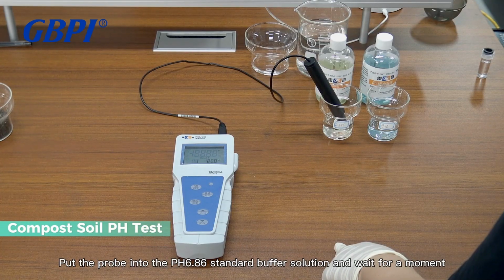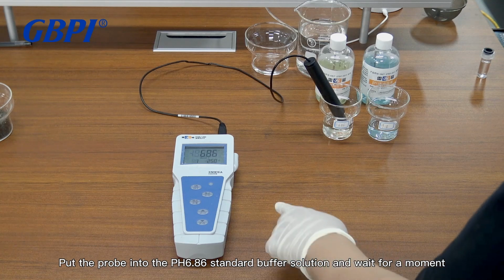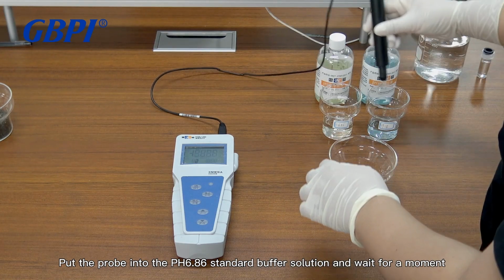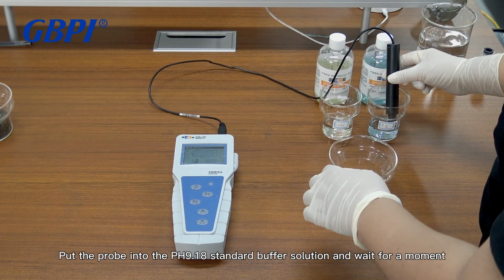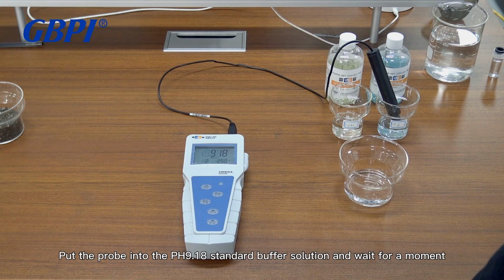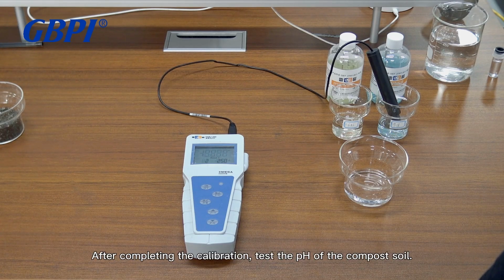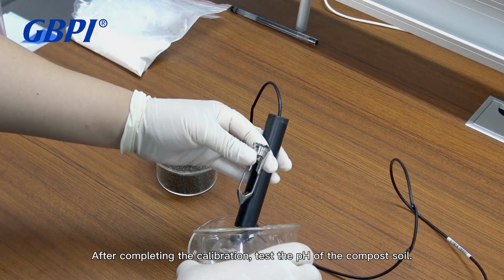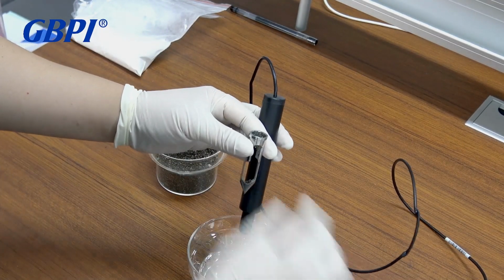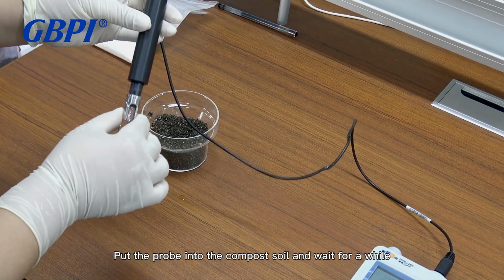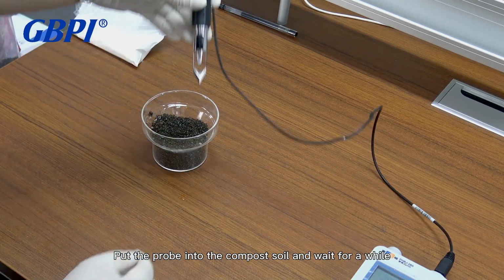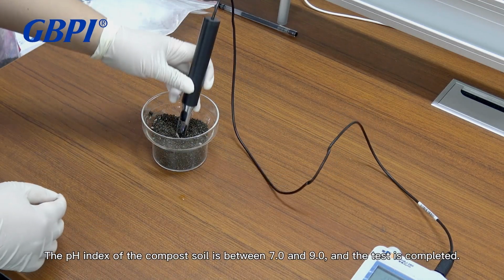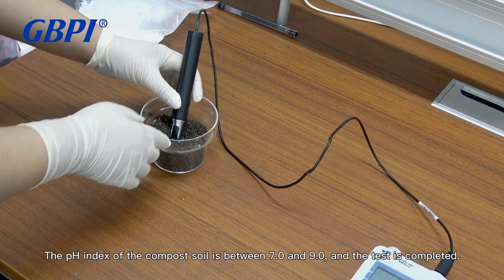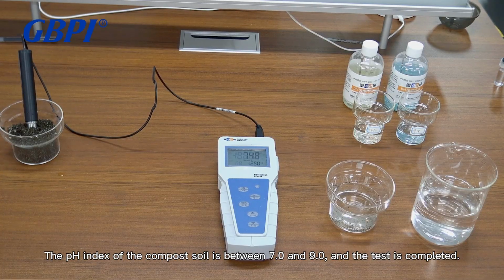Put the probe into the pH 6.86 standard buffer solution and wait for a moment. Put the probe into the pH 9.18 standard buffer solution and wait for a moment. After completing the calibration, test the pH of the compost soil. Put the probe into the compost soil and wait for a while. The pH index of the compost soil is between 7.0 and 9.0, and the test is completed.